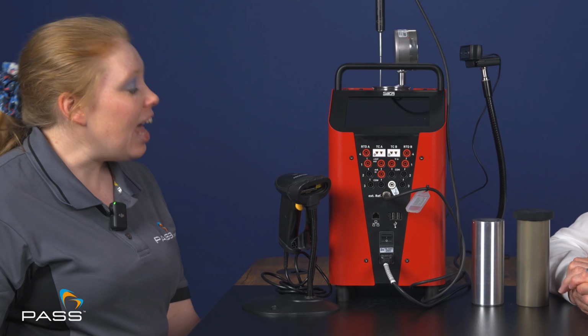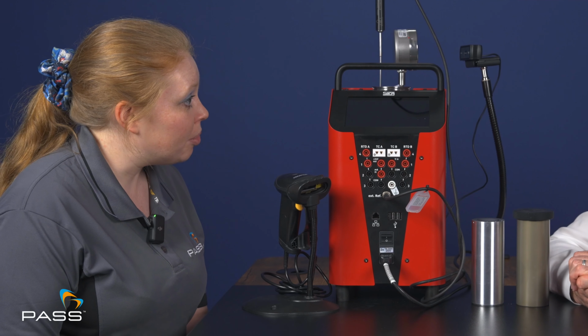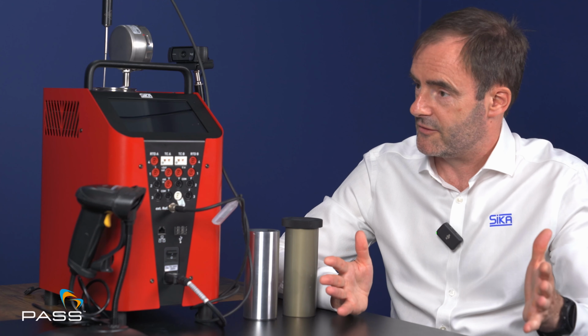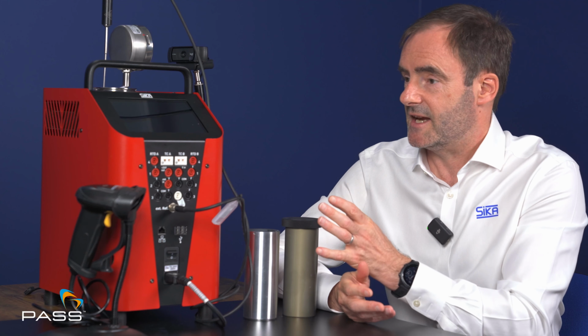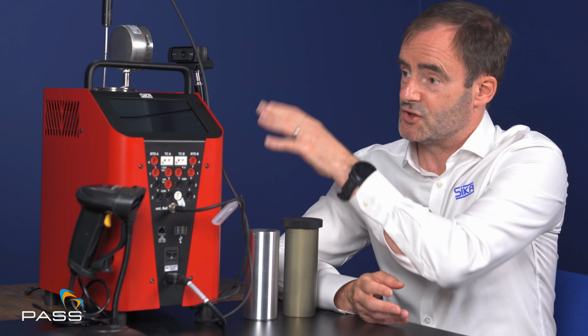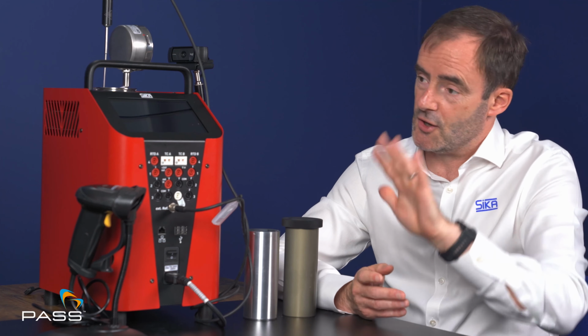Is there anything else you think we should know about the Sika TP Premium temperature calibrators? The TP Premium has various functionality and lots of different features. We can calibrate various different temperature sensors over different temperature ranges, so the breadth of the products that we can calibrate is quite large. The benefit to a customer comes down to how long it takes to calibrate each particular unit. As we mentioned earlier about the Rocket controller, that part of the Sika calibration unit helps reduce the time it takes to calibrate a unit. Especially when we use the two instruments on the front face, a user can set up two sensors within the unit, switch it on, leave it and go away and do something else. So there's a time benefit, which ultimately turns into a cost benefit.